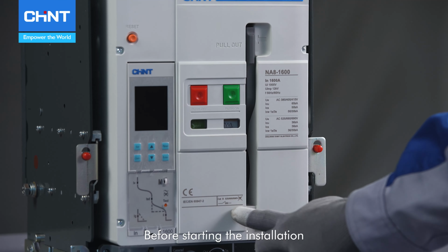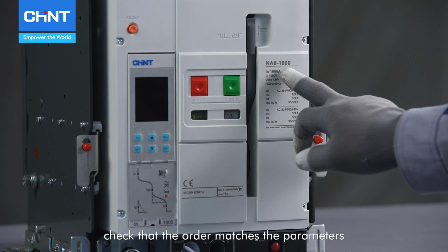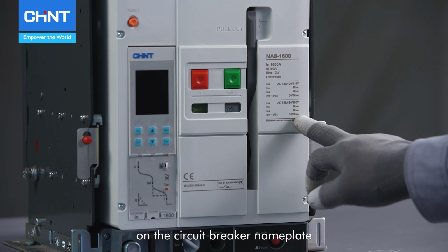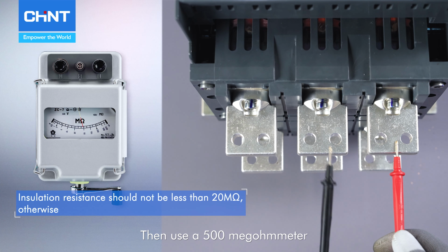Before starting the installation, check that the order matches the parameters on the circuit breaker nameplate. Then use a 500 megohmmeter to check the insulation resistance of the circuit breaker.